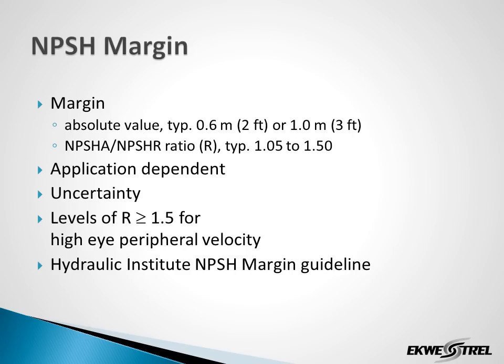Some explanation of NPSH margin: it can be either an absolute value or a ratio — the ratio of NPSH available over NPSH required. NPSH margin ratios in the range of 1.05 to 1.5 are typical. NPSH margin ratios greater than 1.5 may be required for impeller inlet velocities that are quite elevated, such as found in boiler feed pumps, water injection pumps, and other high head pump types. Incidentally, the Hydraulic Institute is close to releasing a new NPSH margin guideline.